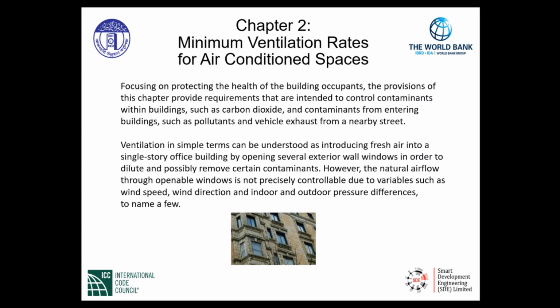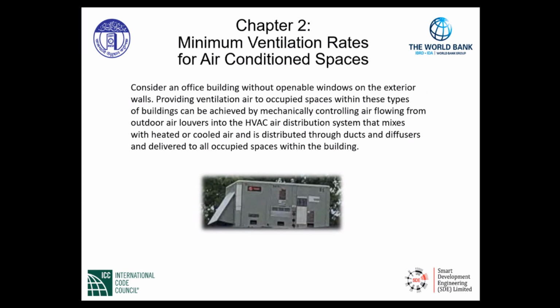However, the natural airflow through openable windows is not precisely controllable due to variables such as wind speed, wind direction, indoor and outdoor pressure differentials or differences, just to name a few. So again, where natural ventilation is allowed by this code, we will find out where it is not precisely controlled. Consider an office building without openable windows on the exterior walls. Providing ventilation air to occupied spaces within these types of buildings can be achieved by mechanically controlling air flowing from outdoor air louvers into the HVAC air distribution system that mixes with heated or cooled air and is distributed throughout ducts and diffusers and delivered to all occupied spaces within the building.